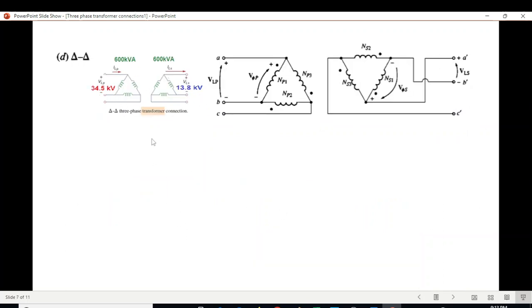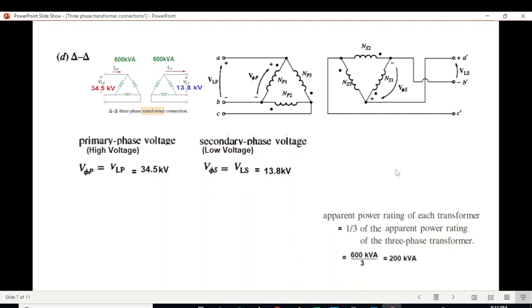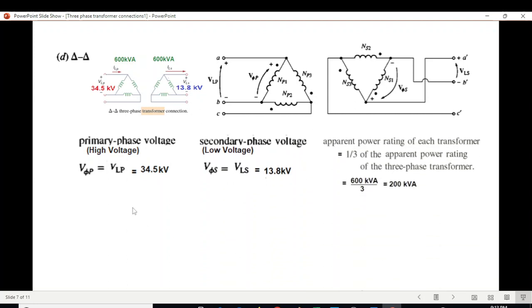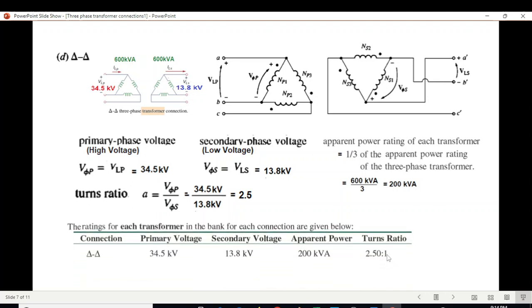Delta-Delta connection: line voltage and phase voltage are the same on primary side and secondary side. So primary phase voltage 34.5, secondary phase voltage 13.8. Power remains the same. Turn ratio calculated is 2.5. In tabular form we enter this. So these are all four basic circuits.